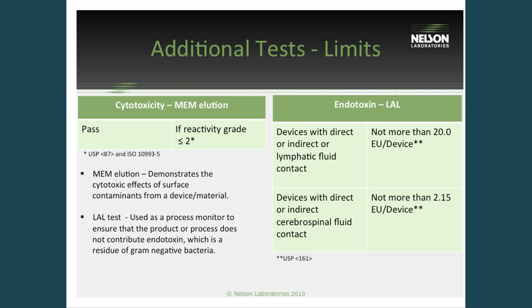We always recommend adding additional tests to the analytical tests such as cytotoxicity, endotoxin, and bioburden — including those tests as part of the cleaning validation to help show additional data about how clean your device is. Endotoxin and bioburden are options lined out in the governing ASTM standard as well. Cytotoxicity is not in there, but we recommend it to show whether the residues obtained are cytotoxic or not. Some of these additional tests have their own acceptance criteria, such as the MEM elution and LAL test methods. So once you've got the quantified number from the analytical tests, if you also have passing cytotoxicity and LAL scores, you can further justify that you have no endotoxin and that the device is non-cytotoxic — helping overall to justify that you have a clean device.